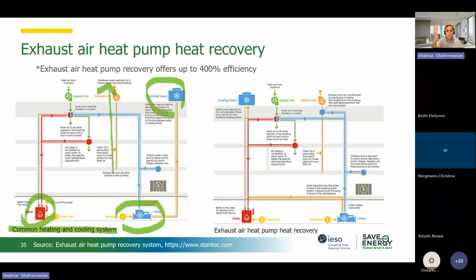So for that reason, the typical application is that they put a fan up and then they just take it out to atmosphere. That's it. But we can install a heat pump or some kind of exchanging system in here, and that exchange system can take the heat and then convert it to cooling, for example, and then send it to the chiller or cooling system that we have.